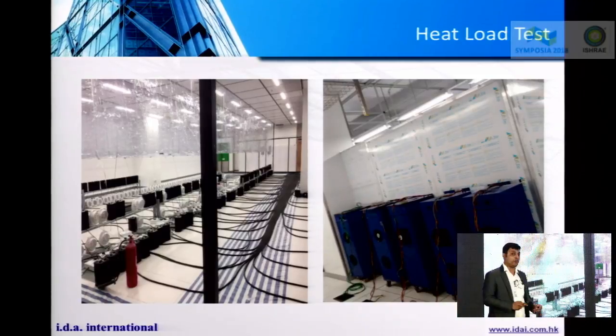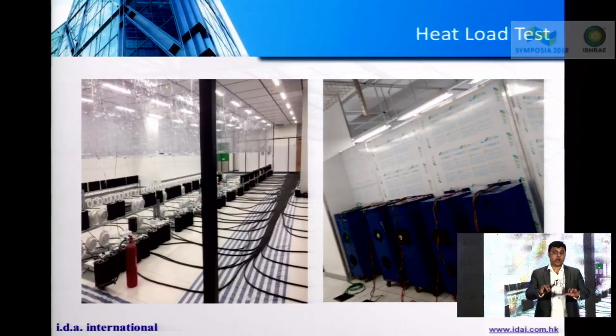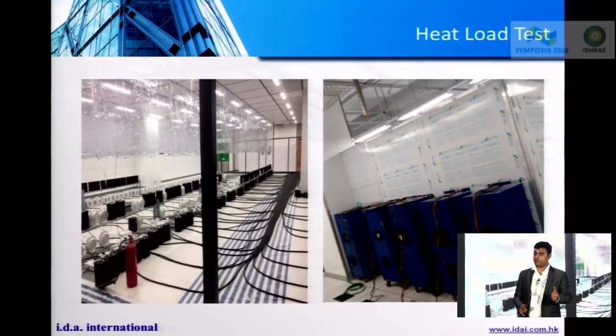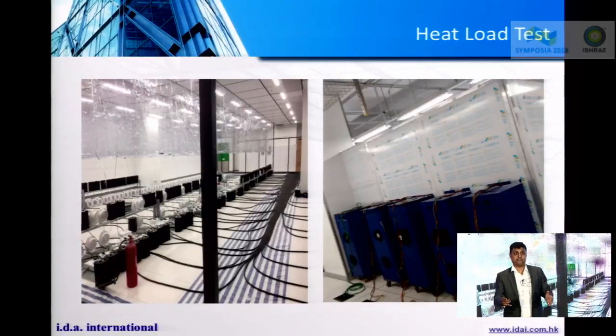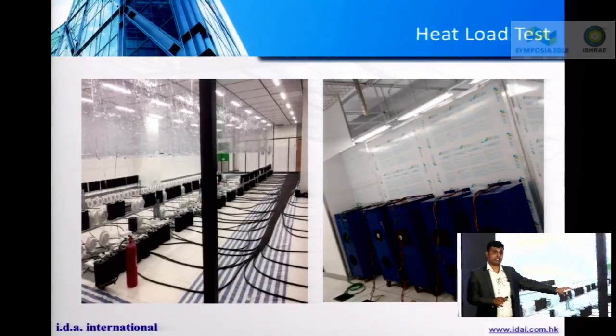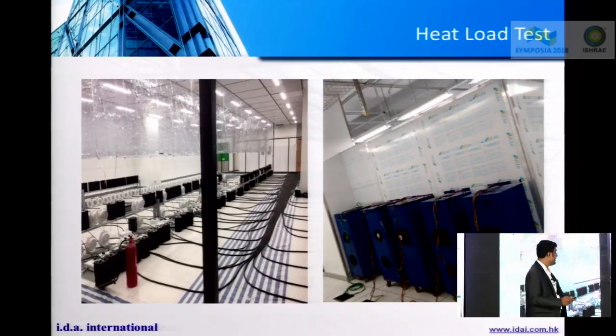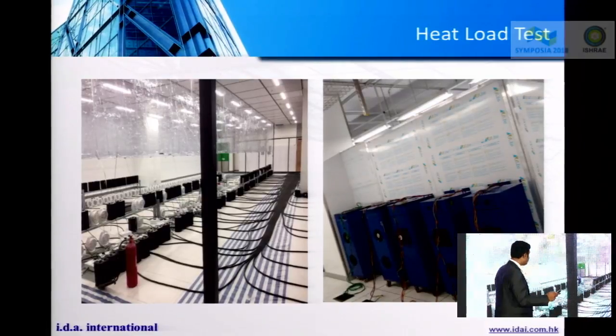The second thing I have to do is create a temporary cold aisle containment. You cannot simulate a heat load test without a temporary cold aisle containment because you have to verify the temperature profile. So this is some of our existing projects where we have done a mock-up heat load test, and this is how it should be arranged.